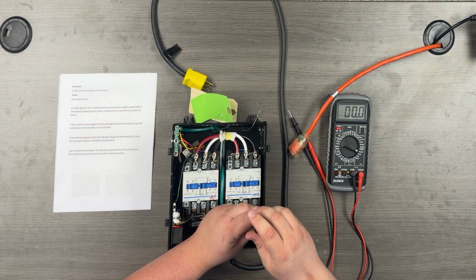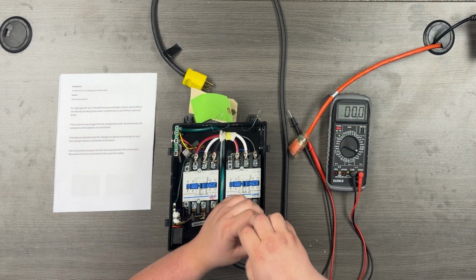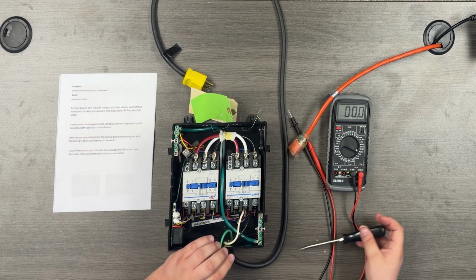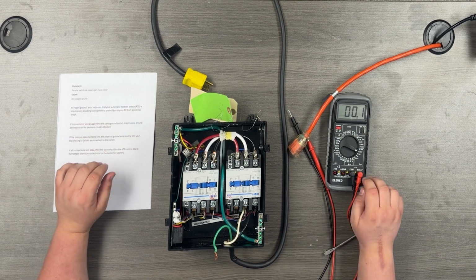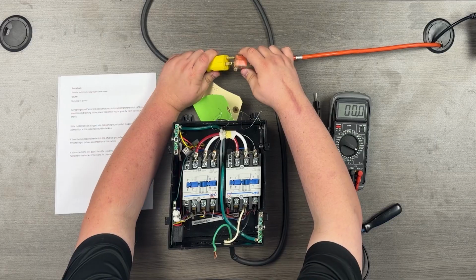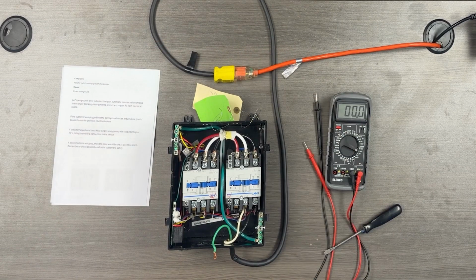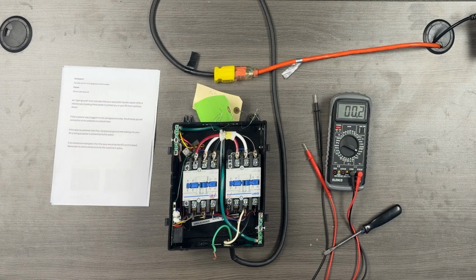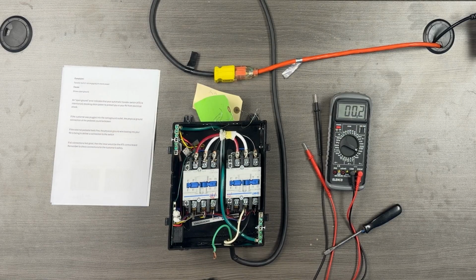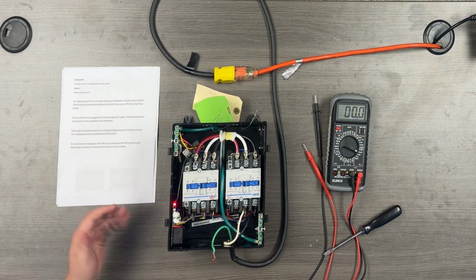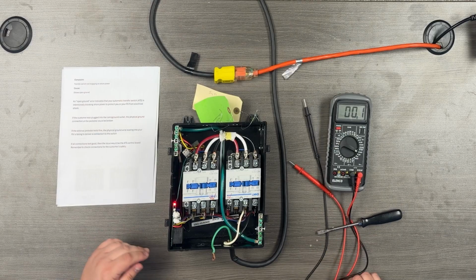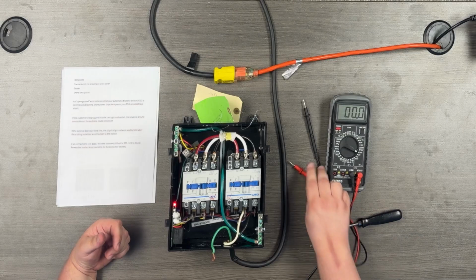I'm going to go ahead and unplug this, and then I'm going to simulate an open ground. With my power disconnected, I'm going to go over here and undo my ground. So now my incoming power does not have ground coming to it. I'm going to hook up my transfer switch, and we should see one of our lights come on the circuit board. There we go. So we see this light came on. This means that the transfer switch has detected that it's got an open ground. It's not allowing power to pass through, as you can see.